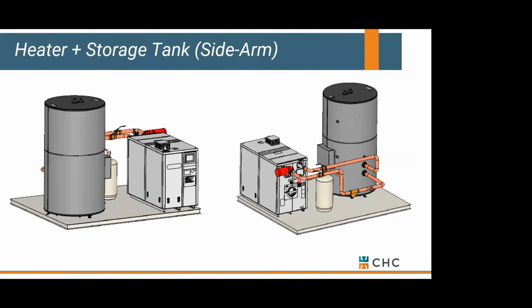And you might think 40 degrees. Yeah, that's not really the case. The whole time we have 40-degree domestic water blending with that 140 in the storage tank. Ultimately, we're probably going to expect 90 to 100 degrees leaving our 140-degree storage tank headed to our water heater. Now if our water heater is condensing, the colder that water is leaving the bottom of our storage tank, the better. That's good for efficiencies.